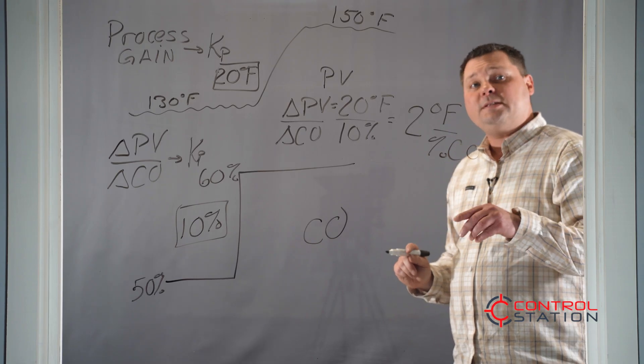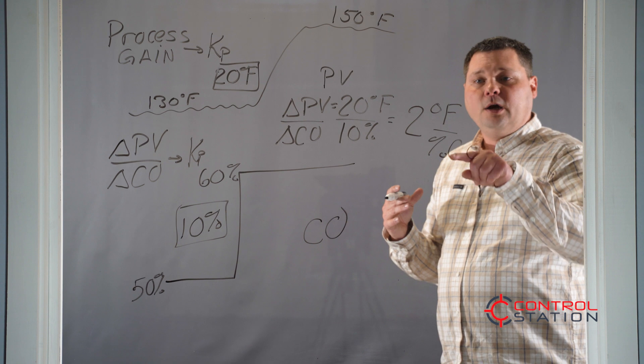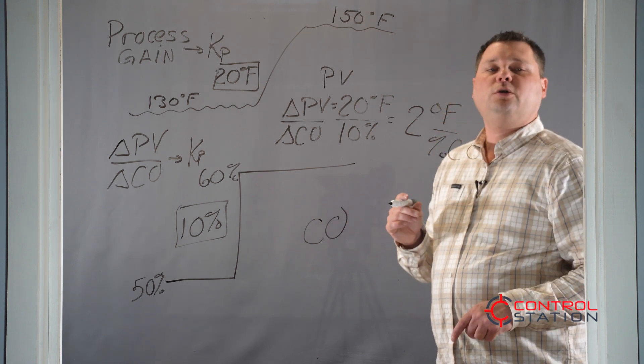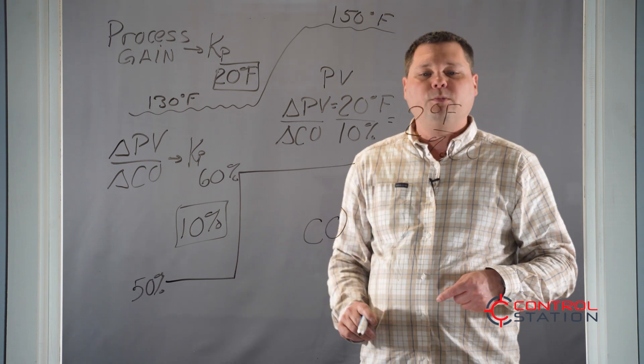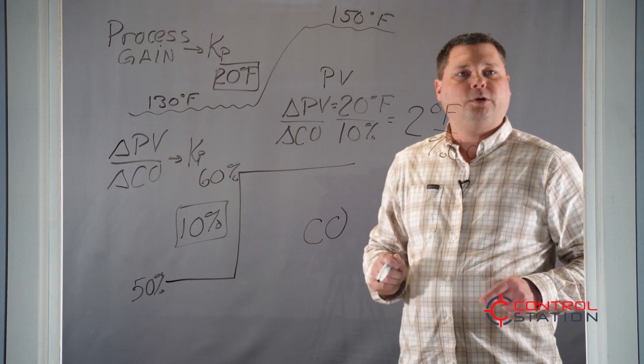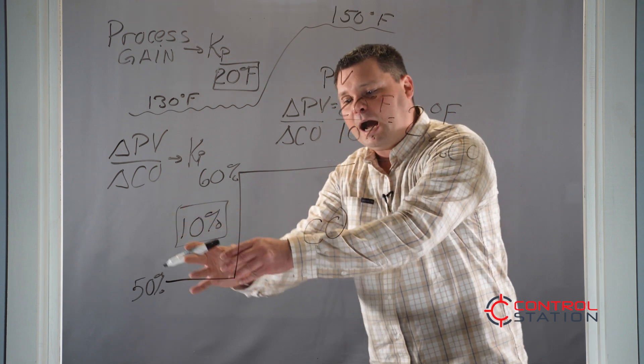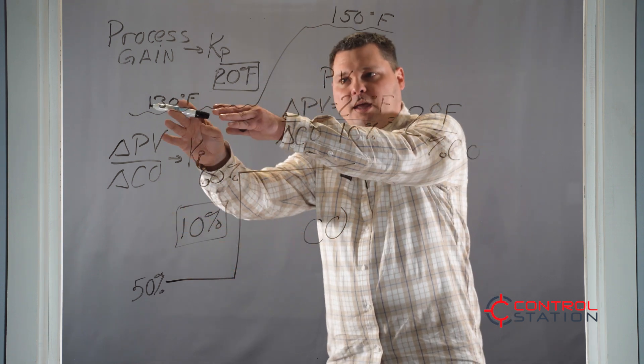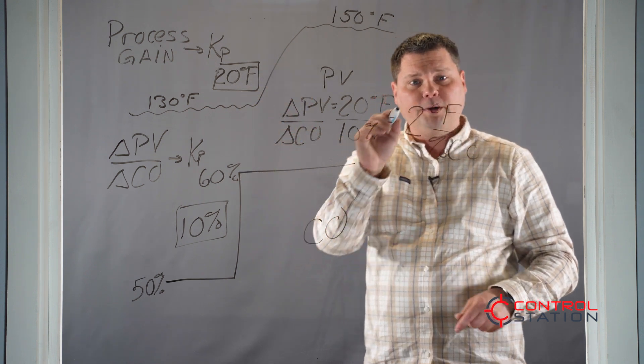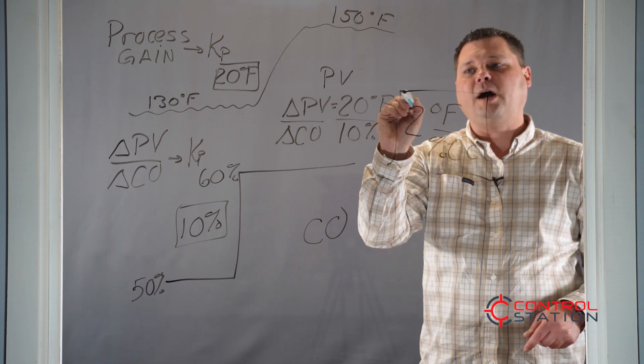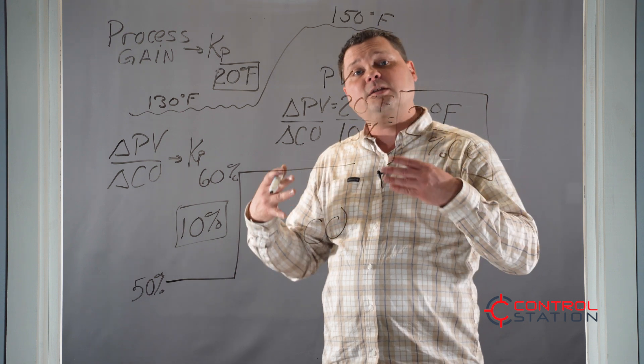What that means is that for every 1 percent we open our control valve — or our pump or whatever it is — our temperature is going to increase by 2 degrees Fahrenheit. It gives us the sensitivity, the how far. So we take the data for how far the controller output was moved, divide the process variable change by the controller output change, and we get our process gain. This tells us how sensitive the process variable is to changes in the output.